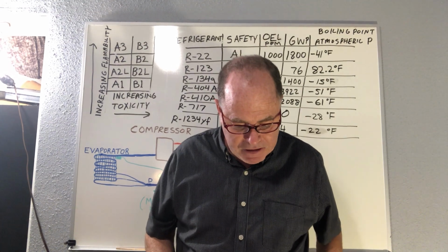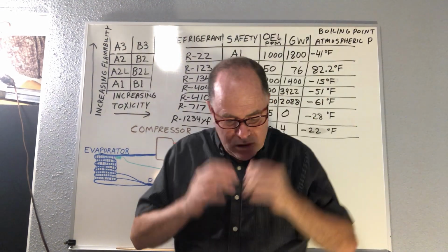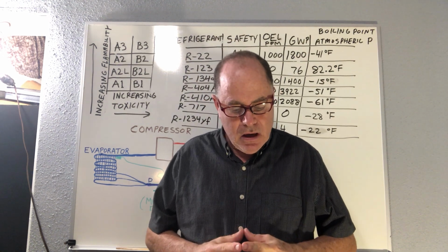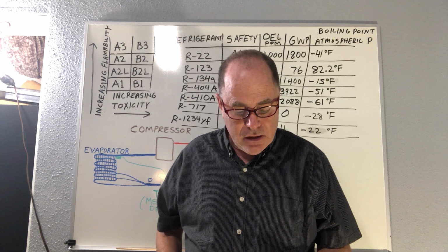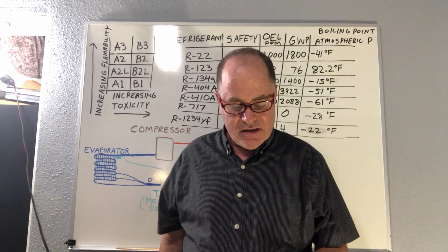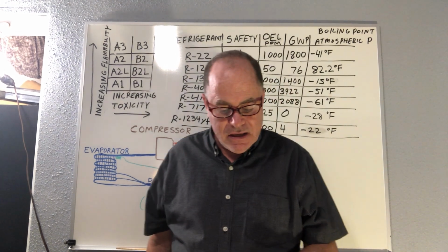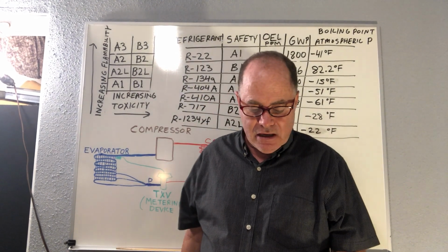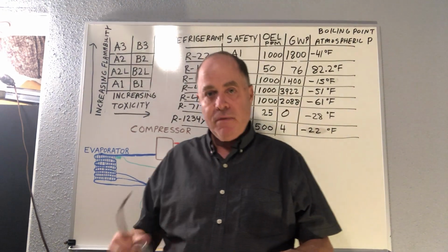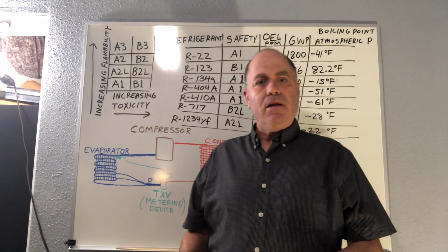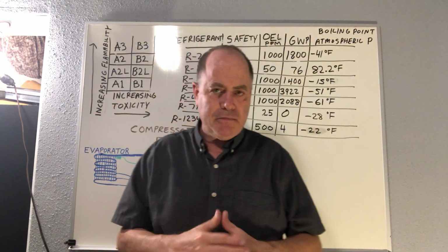Here on ventilated spaces, it says here, where a refrigerating system or a part thereof is located with an air handler in an air distribution duct system or an occupied space served by a mechanical ventilation system, the entire air distribution system shall be analyzed to determine the worst case distribution of a refrigerant leak. So the basic concept, and my teaching style is really just understanding concept.